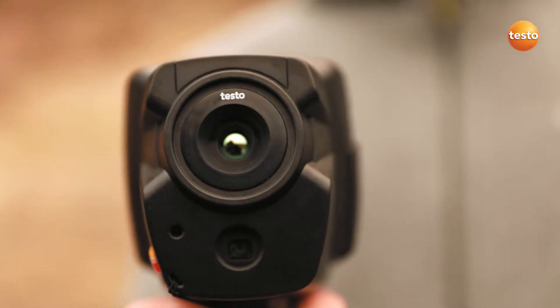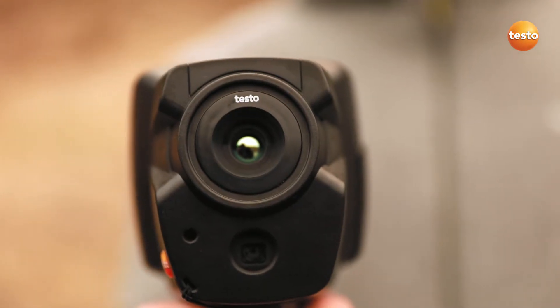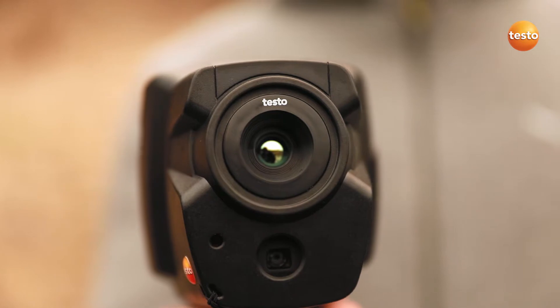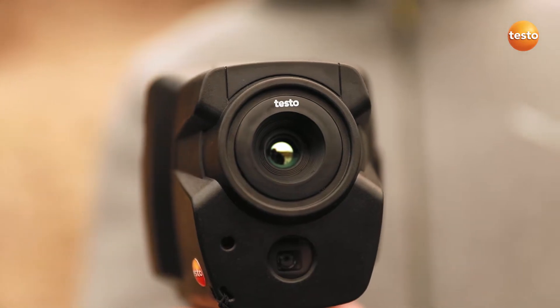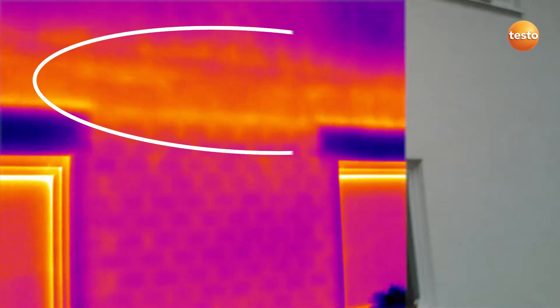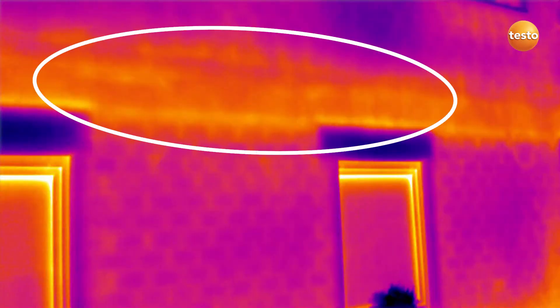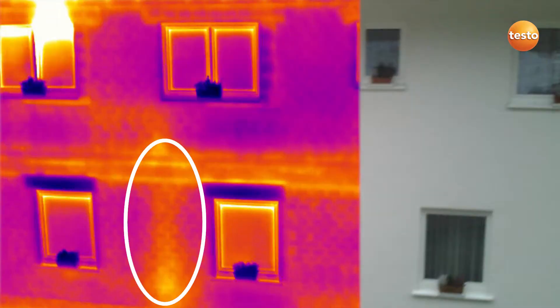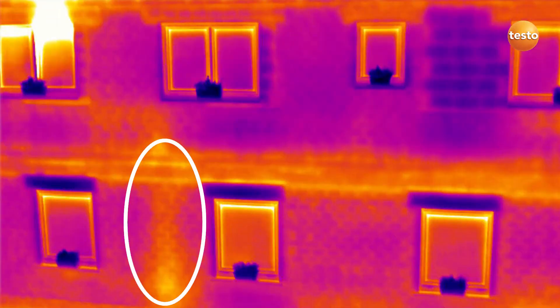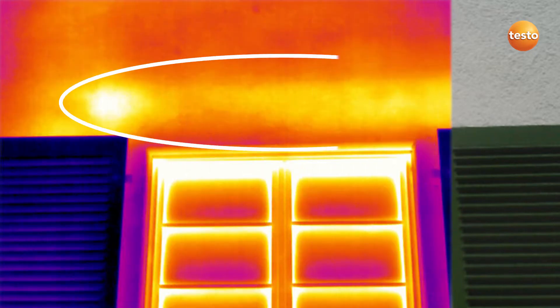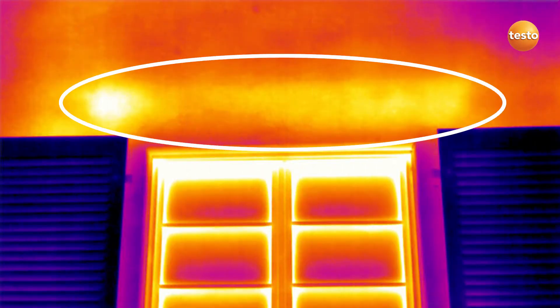Let's see which faults we can identify with Testo 872 on the facade of this building: a cold bridge along the hole of the intermediate floor, the badly insulated riser of a radiator, and an unmistakable air leak at a window lintel.